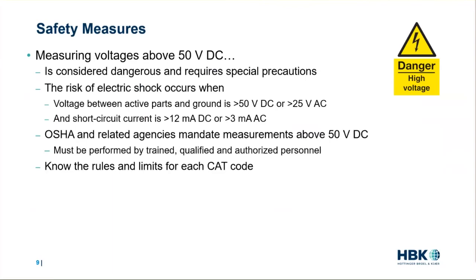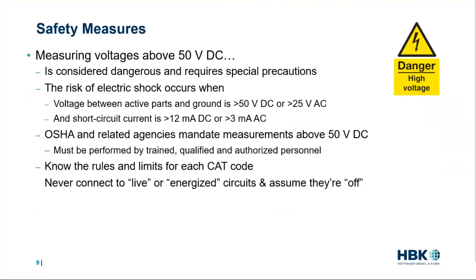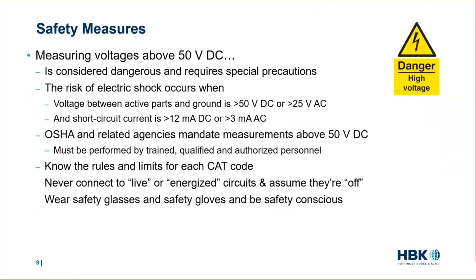So you need to know the rules and limits for each CAT code, and we'll talk more about those CAT codes in a moment. Never connect to live or energized circuits and assume they're off. Wear safety glasses and safety gloves and be safety conscious. And I like this handy tip. Be sure to use one hand when making measurements, because the last thing you want to do is have one hand on a metal pipe while using your other hand to connect to a high voltage point.